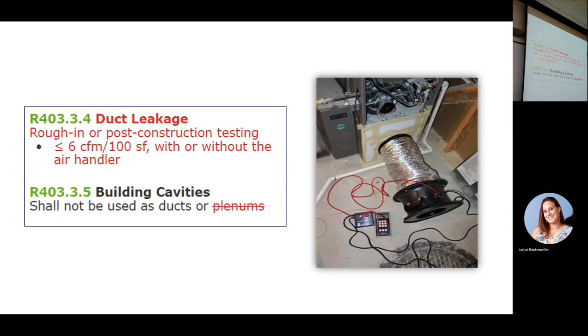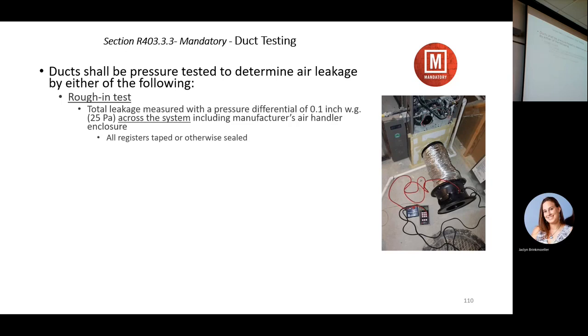Pressurize the duct system only to 25 pascals, half as much as we do our house, and then measure the leakage. And in this case, they just temporarily tape the panel on the blower door of the furnace, mask over all the registers and grills, and pressurize the duct system and see how much it leaks. If you have ducts outside the thermal envelope, you have to do this. If they're inside the thermal envelope, you don't have to.